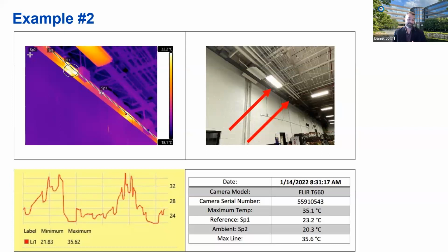And the reason that I wanted to include this particular finding is because it presents a direct fire hazard to the facility. When these bus ducts fail, they tend to fail catastrophically. When that happens, there is typically an arc flash, arc blast associated with the event. We're talking about severe conditions for personnel that would be in the area. And when they do fail, they tend to pour molten copper down on the floor underneath where they are. So this was a great find earlier this year.